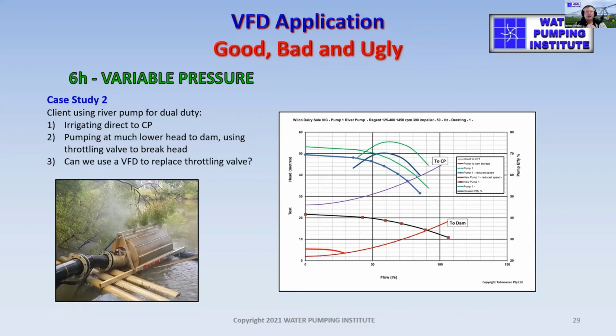So the industry would say, well, fit a VFD. Well, that's great if we could do that. So here's a scenario, a real one that I saw. This is the system curve here. Follow this thin purple line. That was the pumping main to a center pivot. And this is the pump curve here that was feeding the water. So that was the duty point for operation to the center pivot.